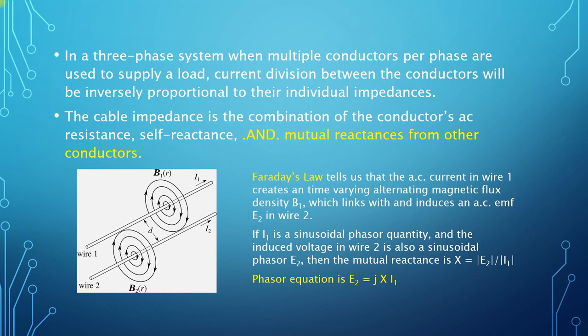When there are multiple paths between a source and a load, the currents will divide between the paths such that the current in each path is inversely proportional to the impedance of the path. Simple circuit analysis tells us this. When cables are arranged in parallel supplying a load, there will be a mutual reactance between the phases, and this mutual reactance increases as the distance between the conductors gets smaller. The AC voltage drop in one cable conductor due to the AC current in a second conductor increases with the current in the second circuit — this is basically a voltage induced by transformer action, i.e. it is an example of Faraday's law.